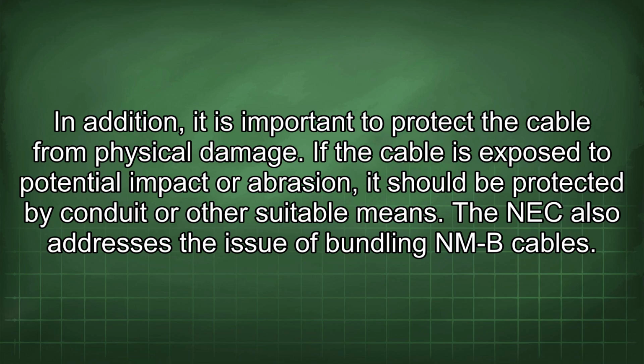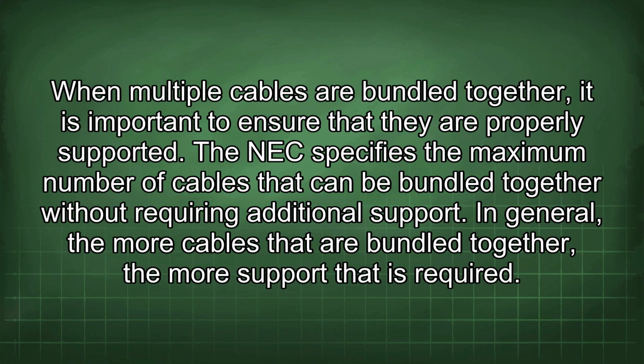The NEC also addresses the issue of bundling NMB cables. When multiple cables are bundled together, it is important to ensure that they are properly supported. The NEC specifies the maximum number of cables that can be bundled together without requiring additional support. In general, the more cables that are bundled together, the more support that is required.